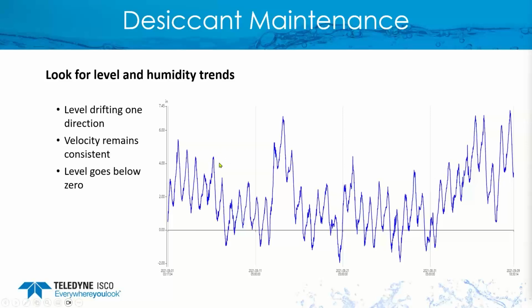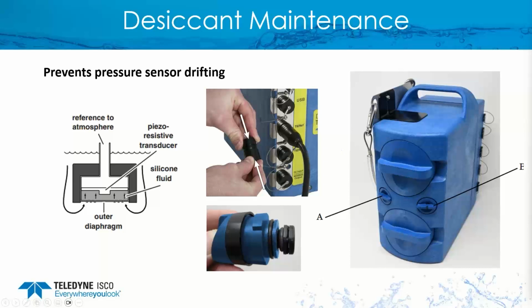And the other thing you may notice with the velocity remaining the same is that, like on the Teledyne ISCO AV sensors, if the level were to drop below zero, it stops trying to read the velocity, and so you'd end up just seeing a flat line on the velocity because the level is too low. Now, let's take a closer look at this.